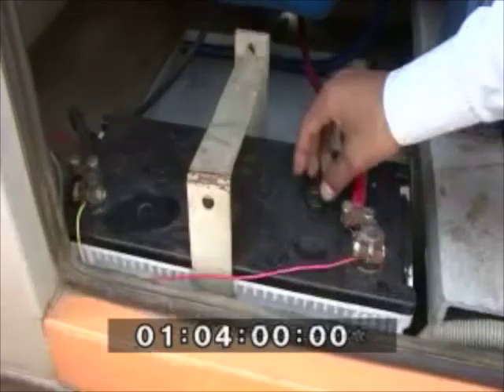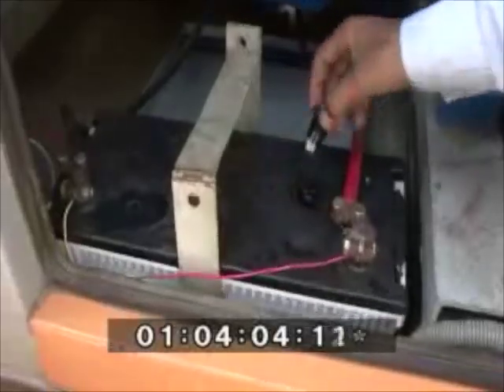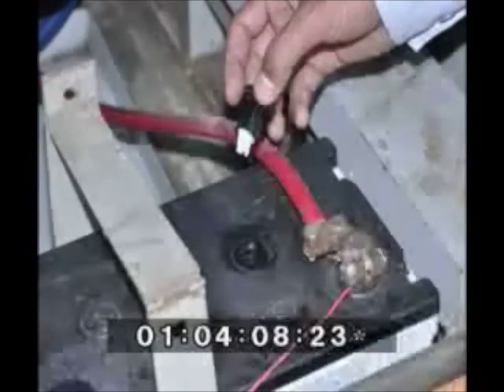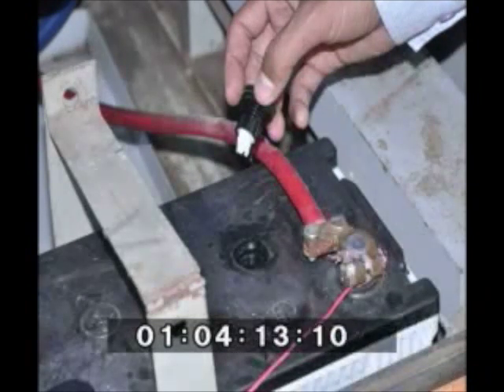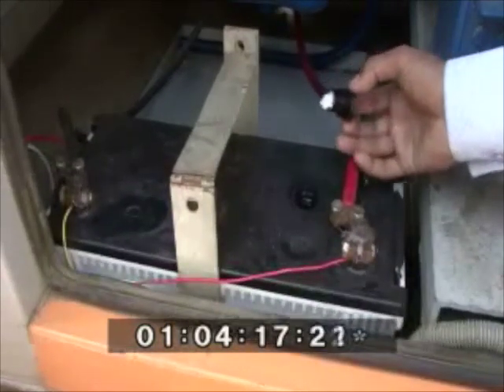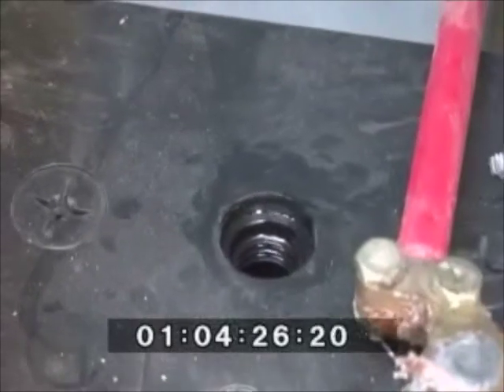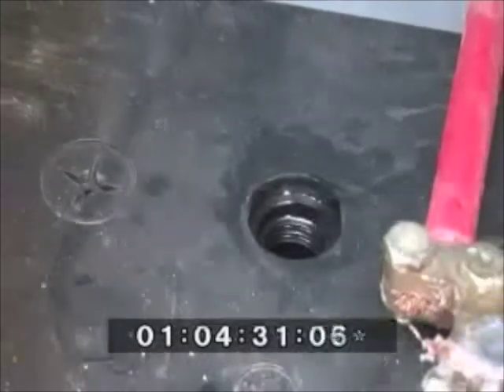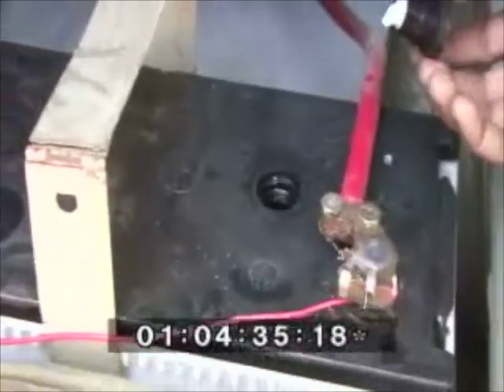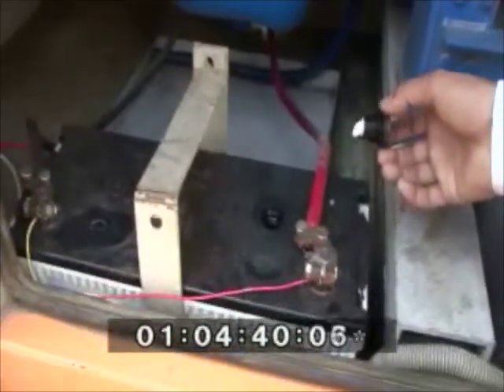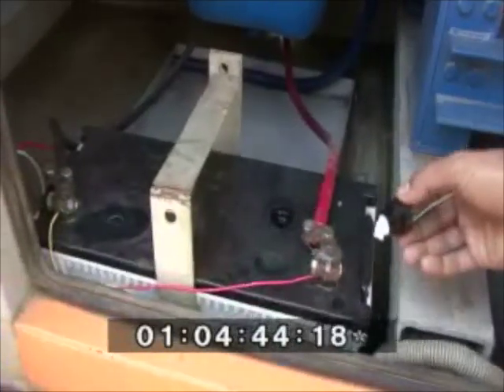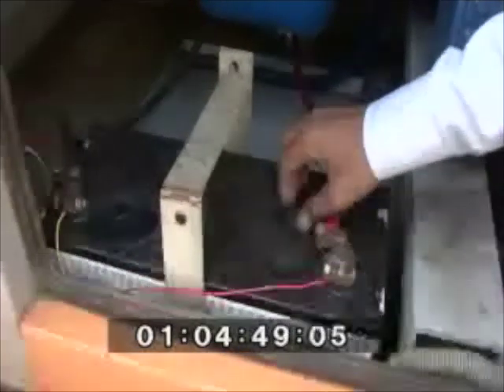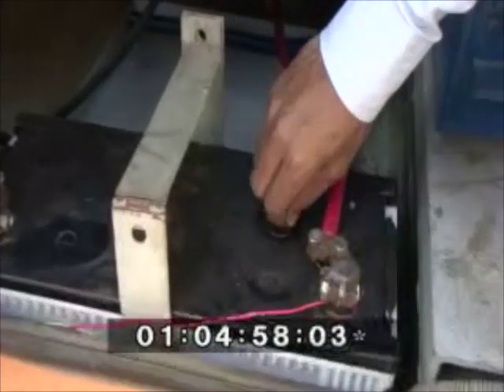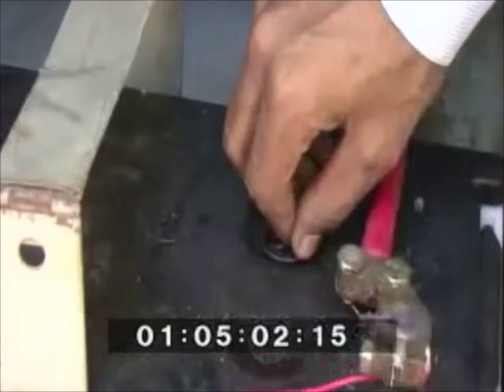Now we will be checking the distilled water in the batteries. To check the level of distilled water in the battery, we need to first open the cap on the cells by unscrewing it. Then we shall see if there is any distilled water inside or not, and whether the battery cells are properly immersed in water or not. In case the level is okay, we replace the lid. If the water is not up to the desired level, then we need to pour distilled water in it so that the cells are totally immersed, and then replace the lid. This check should be done every 15 days.